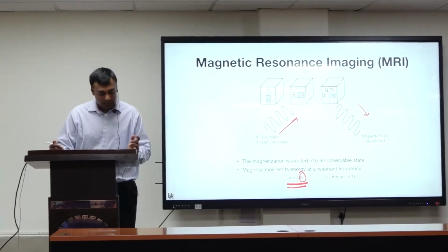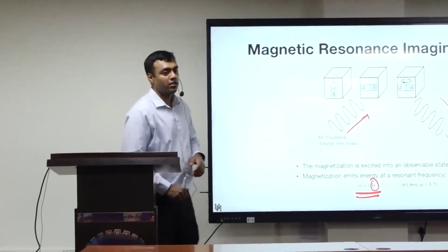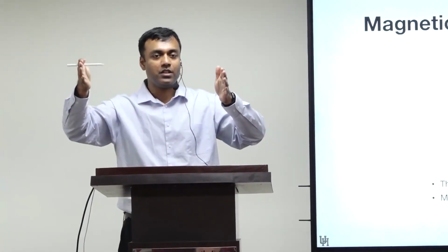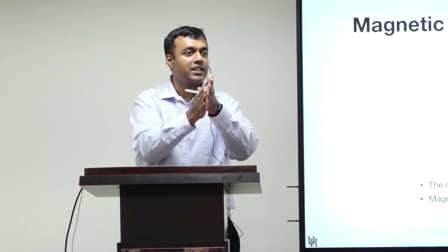This was again a Nobel Prize winning idea. What the scientists figured out was to apply a gradient of a magnetic field inside the human body, high, and lower and lower until low. Now if you send a radio wave and you get a frequency back, the highest frequency will be where the highest magnetic field is. A slightly lower frequency will correspond to a slightly lower magnetic field.